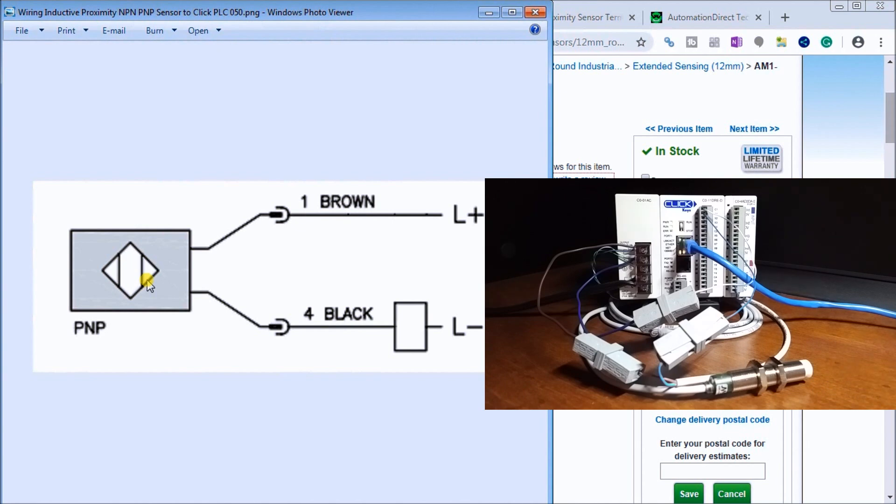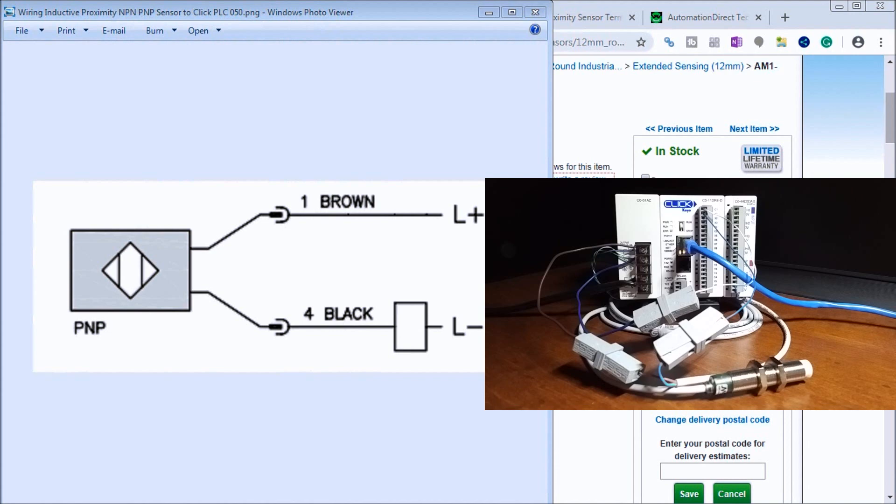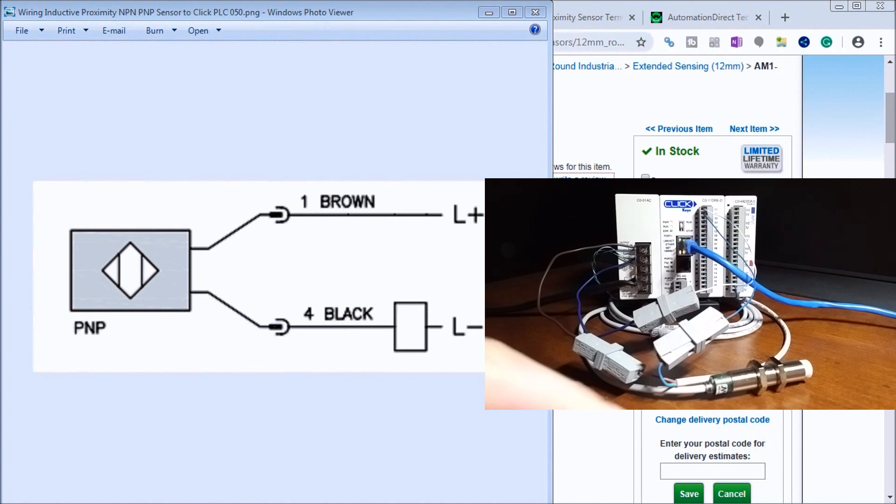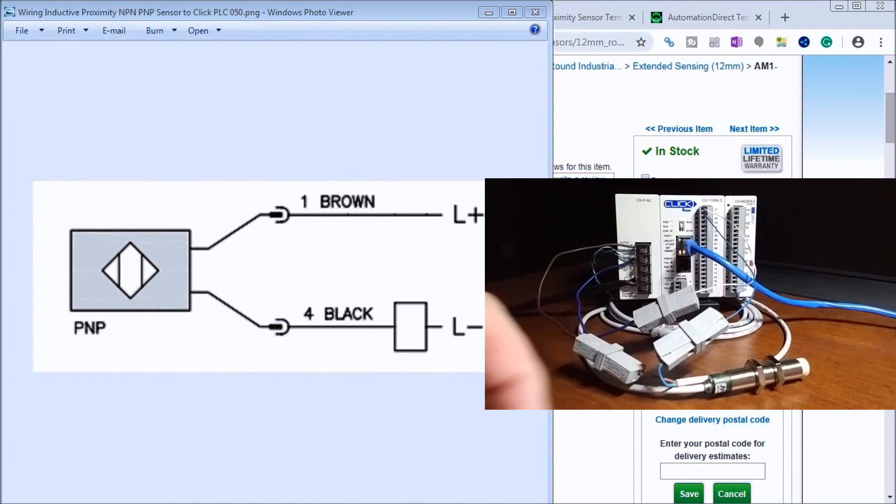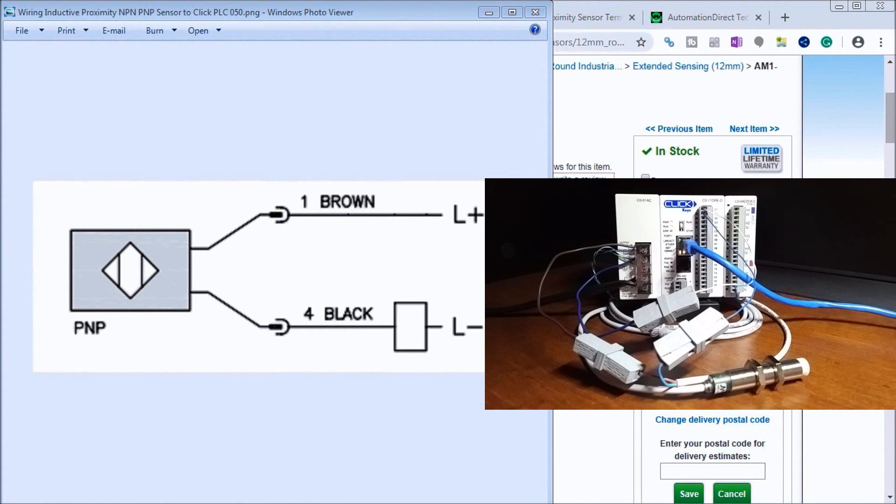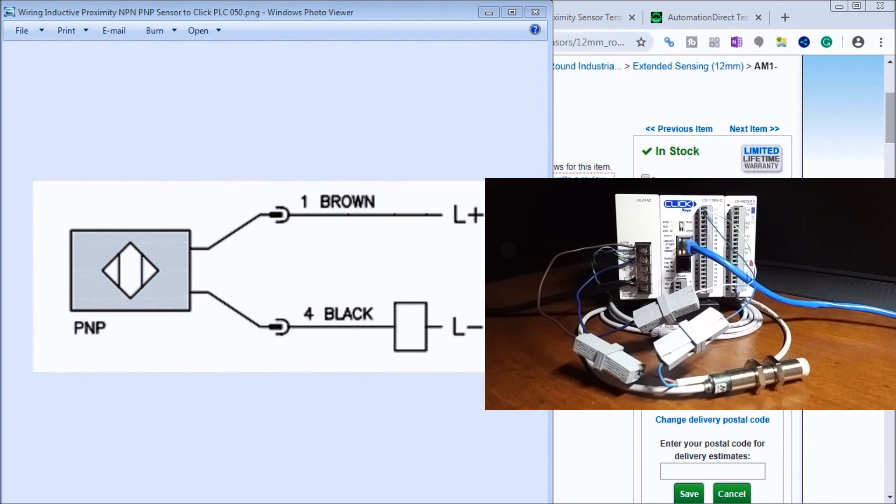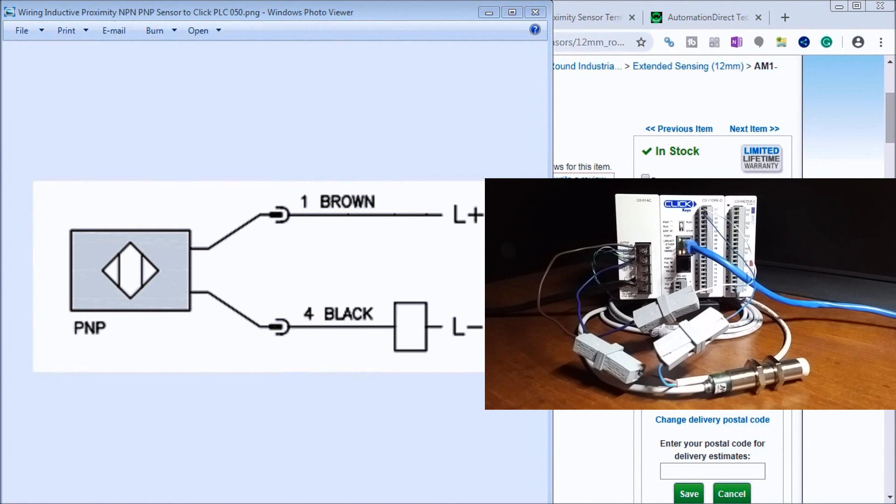One sensor can do NPN or PNP. Common things you'll notice with two-wire sensors is they typically have less of a switching frequency. In our particular case, this sensor will have a switching frequency of 750 Hertz. Then we have a leakage current which is the off state of the sensor and its ability to still drop current even when it's off. On the two-wire it's less than 0.8 of a milliamp, which is very small compared to a three-wire which has less than 120 microamps.